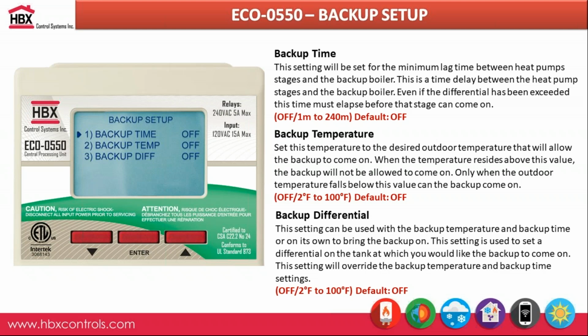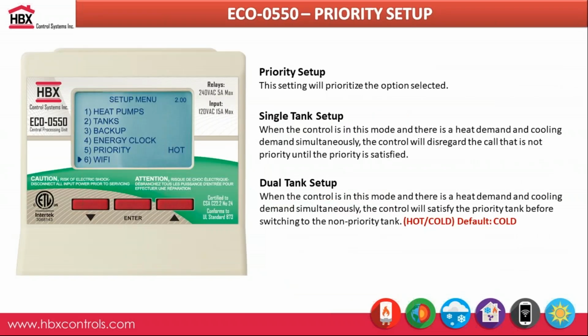We don't have an option to run the backup boiler only on the Eco 550. You could do it with the Eco Switch, but we don't have that option like you do with the Eco 1000. And that's an option that we're probably going to be implementing sometime later this year, because that's a really popular option with the 1000 that some people would like to have on the Eco 550 as well. Again, you can have that backup boiler come on off of tank temperature as well. So you have two different options of when you want that backup to fire up.